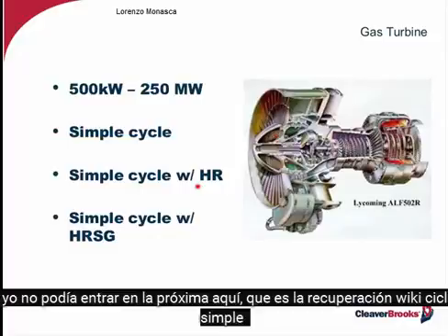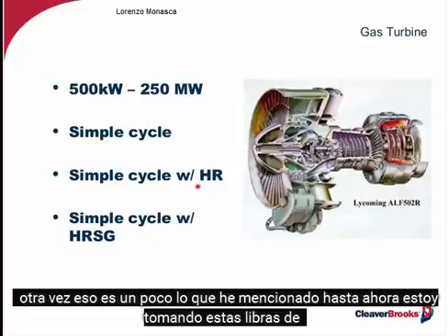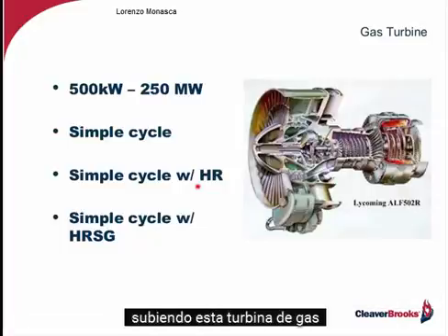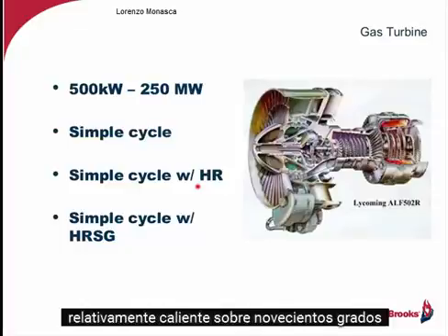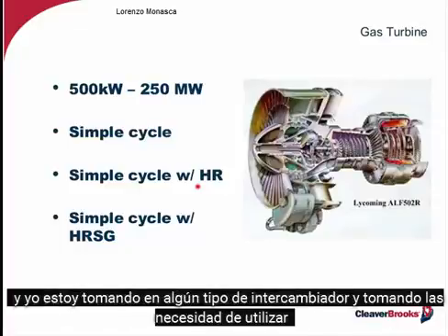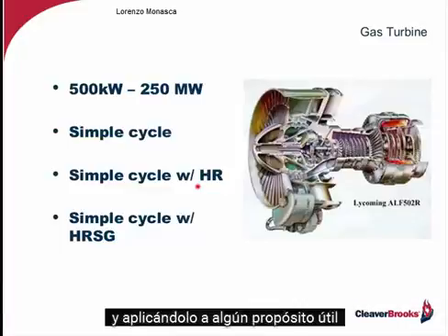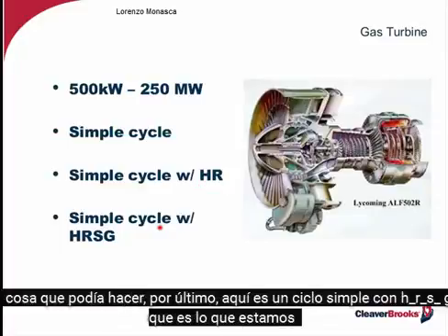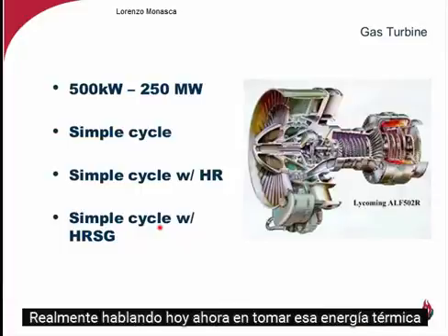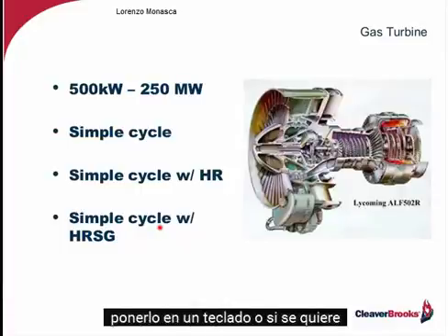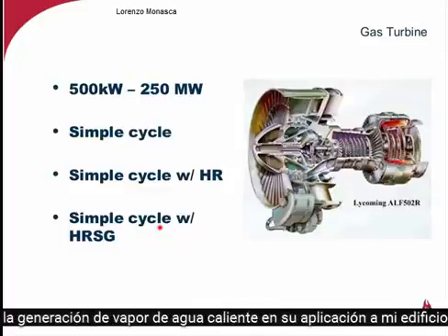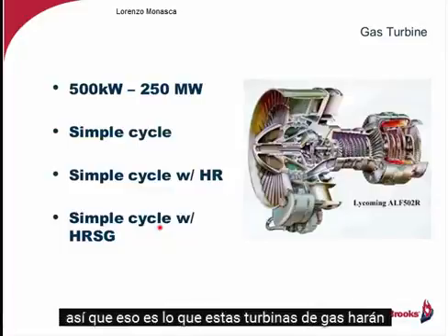I could then get into the next one here, which is simple cycle with heat recovery. Again, that's kind of what I mentioned before. Now I'm taking these pounds of gas coming off this gas turbine, relatively hot, about 900 degrees, and I'm taking it into some kind of an exchanger and taking those BTUs and applying it to some useful purpose. The other thing I could do lastly here is a simple cycle with HRSG, which is what we're really talking about today. Now I'm taking that thermal energy, putting it into a boiler, if you will, generating steam or hot water, and applying it to my building. So that's what these gas turbines will do.